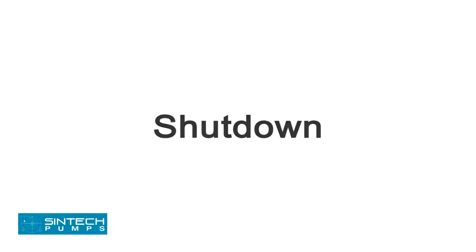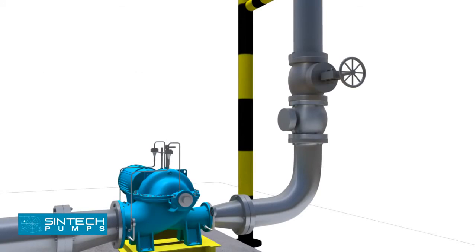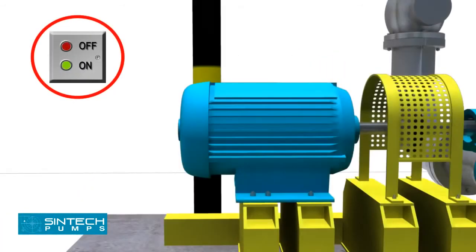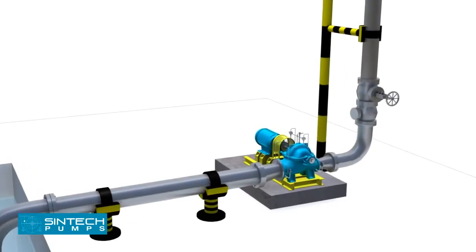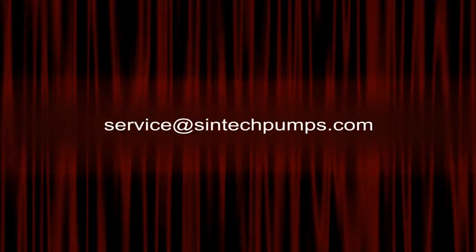Shutdown. The pump may be stopped with the discharge valve open without causing damage. However, in order to prevent water hammer effects, the discharge valve should be closed first. Then stop the driver. Close the water seal valves. Close the valve in the pump suction line if fitted. If danger of freezing exists, drain the pump completely. For further information, you can email your queries to Sintech Pumps.